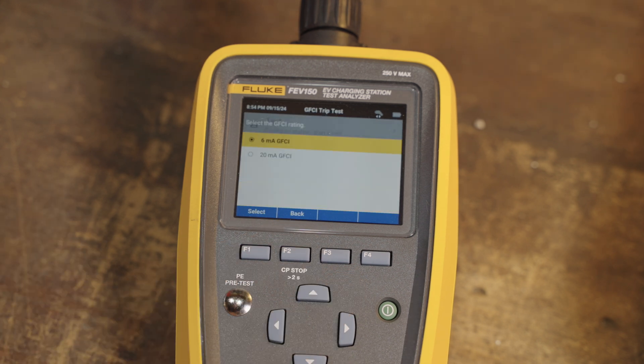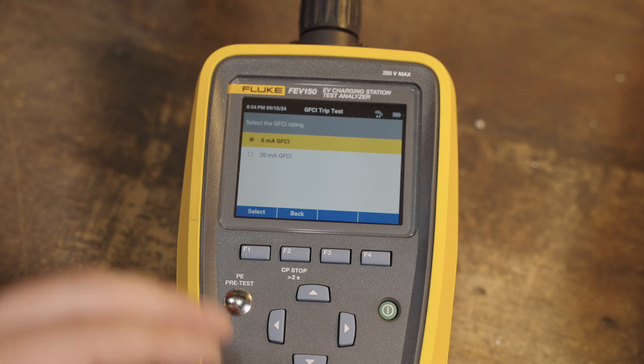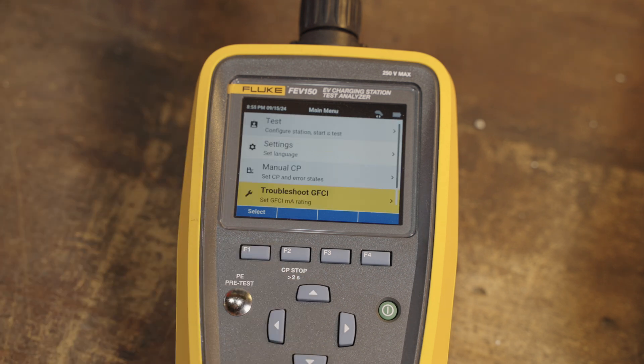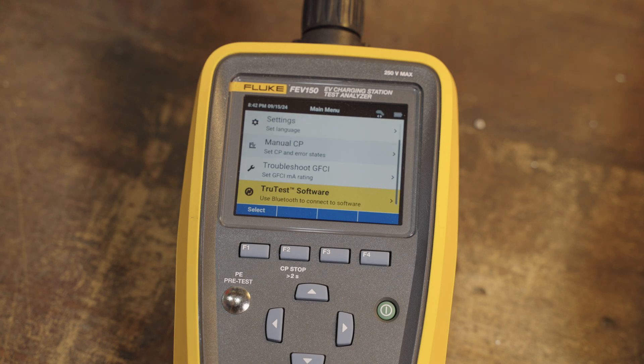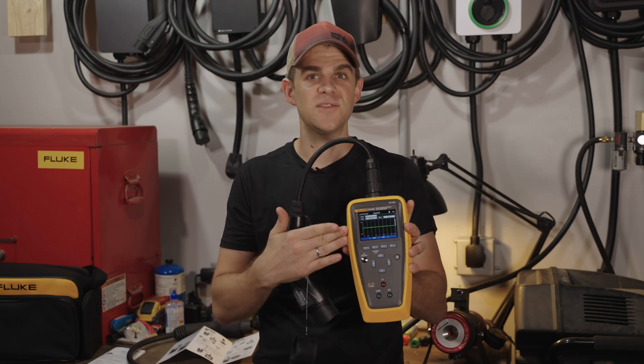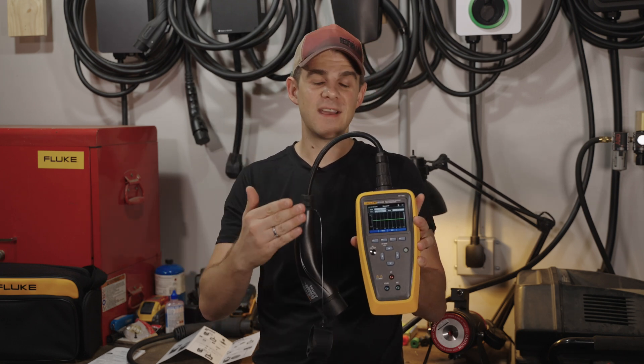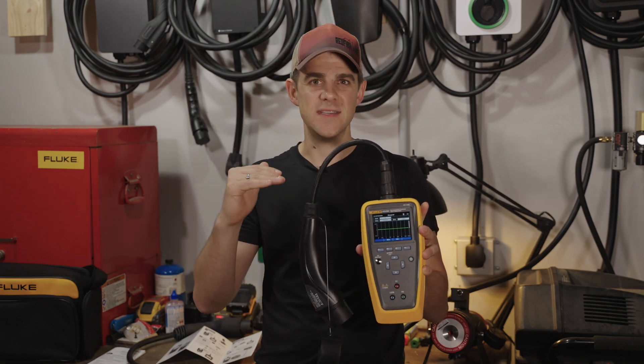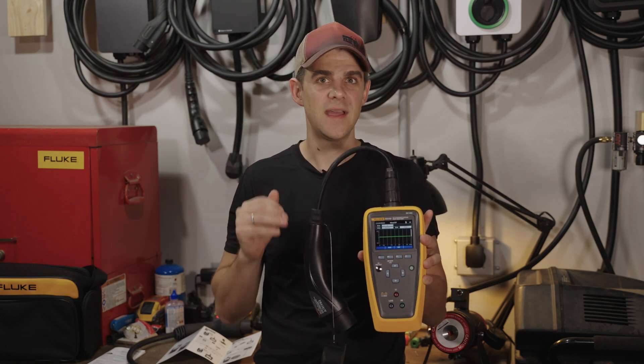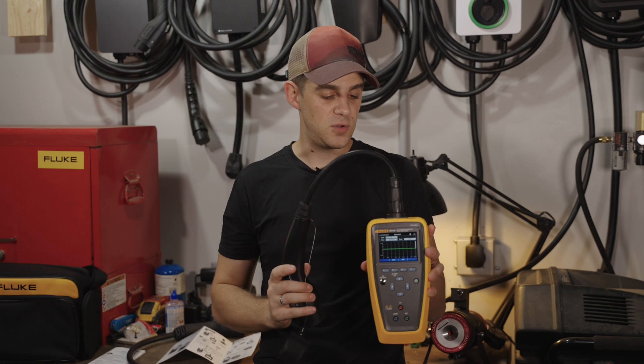We'll look at the GFCI menu — in here you can change the GFCI trip point from 6 milliamps to 20 milliamps, and that's pretty much the only setting in there. The final thing is the TruTest software. If you have the TruTest software on your computer, you can actually link this to your account. So that kind of runs through all the features — this thing is really made for technicians who are out there running through all kinds of tests, wanting to automate that procedure and have a checklist to make sure they've completed every test they need to.